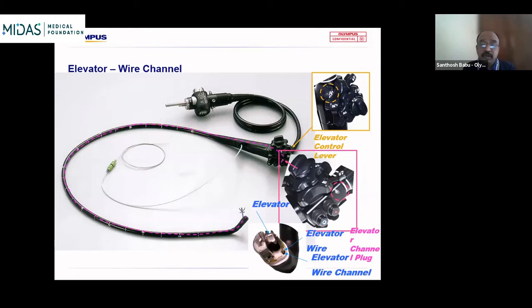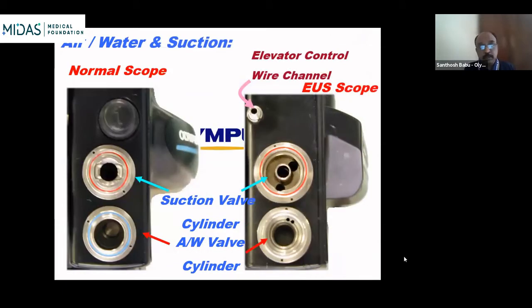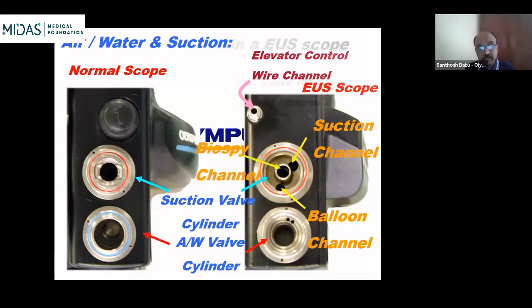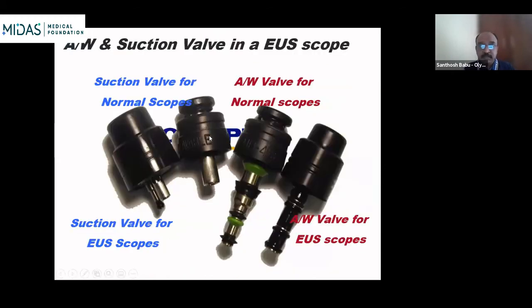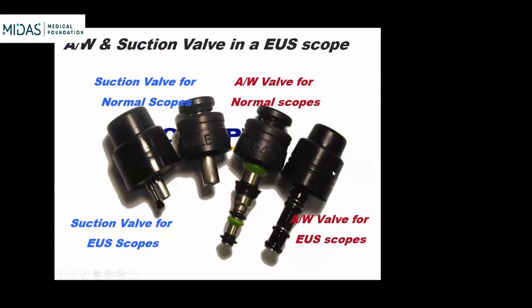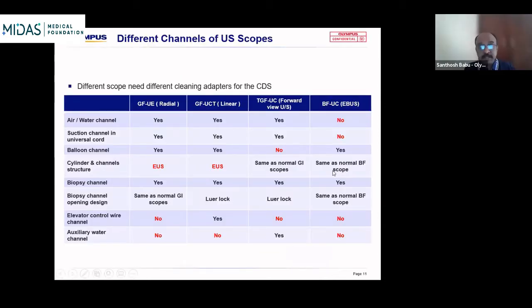Now, something which is not common in the regular endoscopes is these two channels, the balloon suction channel and the balloon water channel. So when I was talking about the channels, you'll also have to know which channels are brushable. Yes, only the suction channel is brushable and the balloon suction channel is again brushable. So these are the two channels that you can brush. The others, you rinse them off, you flush them with the fluids that flow through. Valves are different. The regular valve is something like this. This is your regular suction valve, your regular air water valve. The extreme ends are for the ultrasound valves, both for suction as well as air water. So different channels, yes, it's important to know how your channels are, so that it makes life easier for you to access them and clean them post procedure.